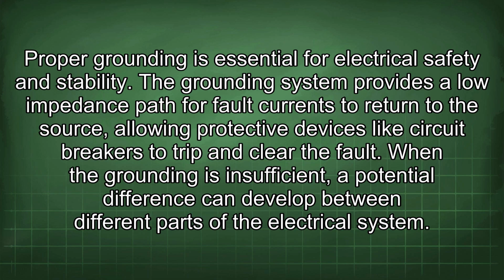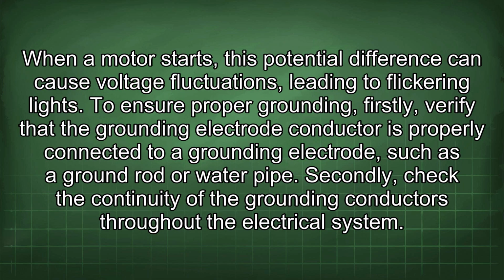The grounding system provides a low impedance path for fault currents to return to the source, allowing protective devices like circuit breakers to trip and clear the fault. When the grounding is insufficient, a potential difference can develop between different parts of the electrical system. When a motor starts, this potential difference can cause voltage fluctuations, leading to flickering light. To ensure proper grounding, firstly, verify that the grounding electrode conductor is properly connected to a grounding electrode, such as a ground rod or water pipe.